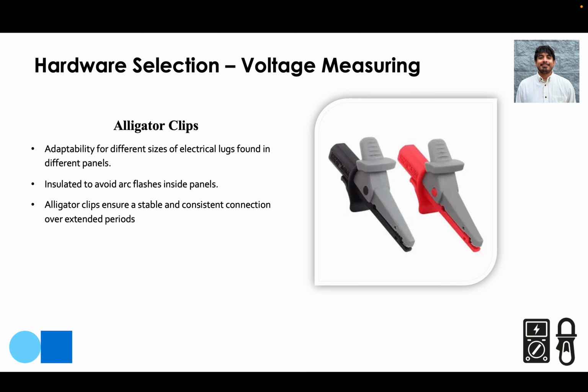For voltage measurement, we selected insulated alligator clips. This configuration gives us high adaptability, allowing our probes to connect to various bus bar sizes inside commercial panels. The insulation on the clips plays a critical safety role and reduces the risk of arc flash and accidental shorts during installation and operation.